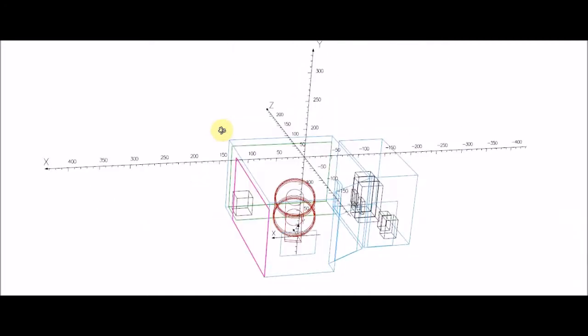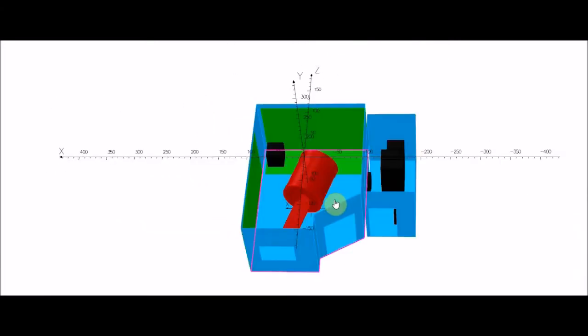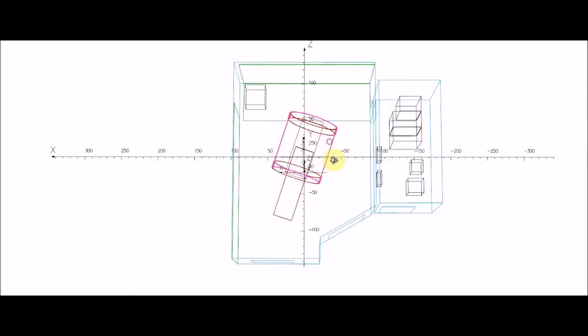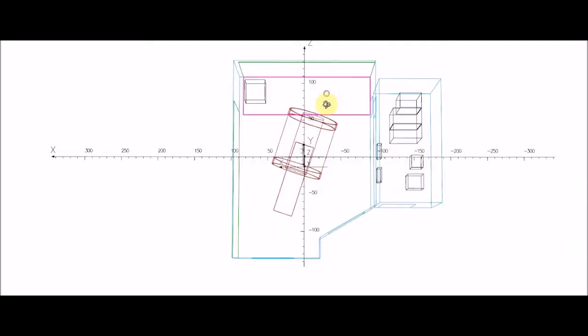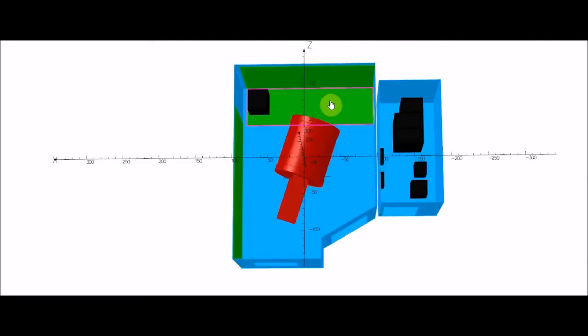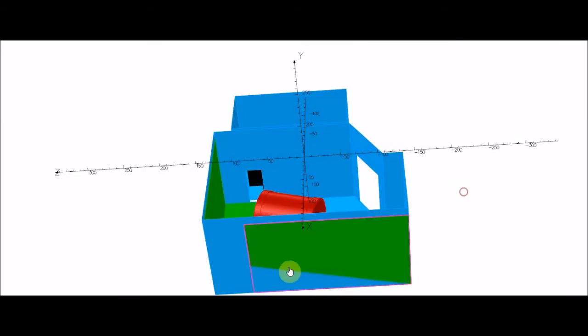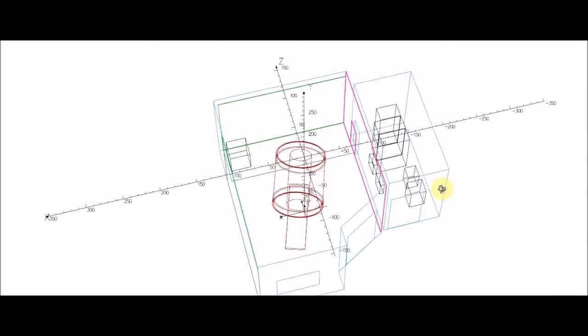And I'll, in another video later on, I'll show the Gauss lines how they actually react with and without the steel. The toe plate or the floor plate here is necessary because the magnet sits low to the ground. ISO center sits low to the ground. So without this toe plate or floor plate, the Gauss lines will sneak out underneath and end up out in the public area. So that's why that has to be there.